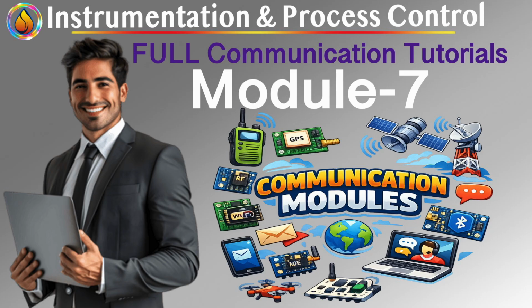Why this idea was so attractive to the process industry. Foundation Fieldbus aligned perfectly with process plant realities: slow-changing processes, high emphasis on diagnostics, long cable runs, hazardous areas, need for intrinsic safety, and desire to reduce cabinets and controllers. By embedding intelligence into instruments, wiring reduces, cabinets shrink, and diagnostics explode in a good way. And because function blocks are standardized, engineers can reason about behavior, not vendor quirks.